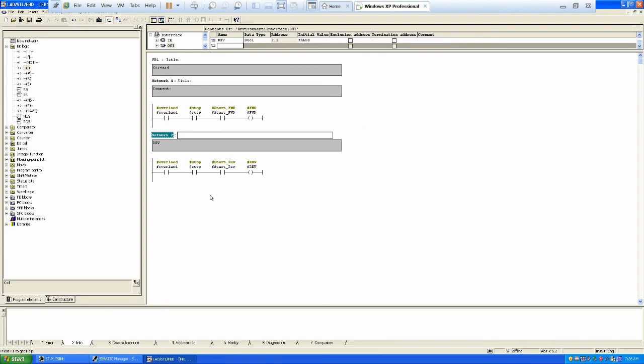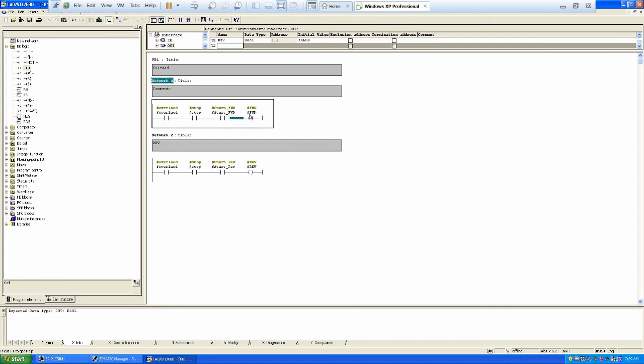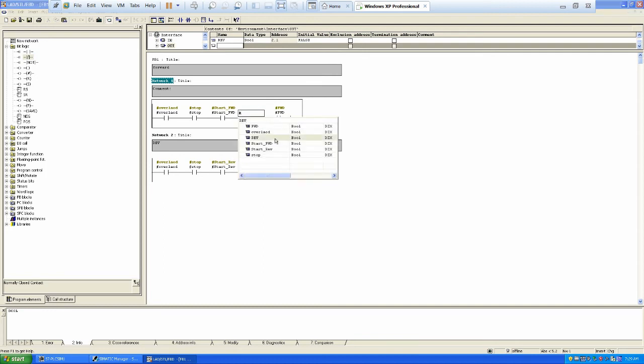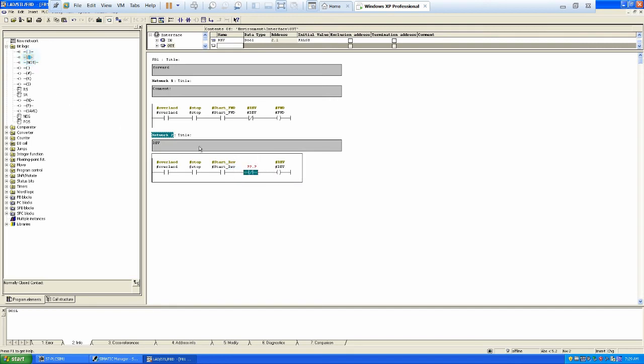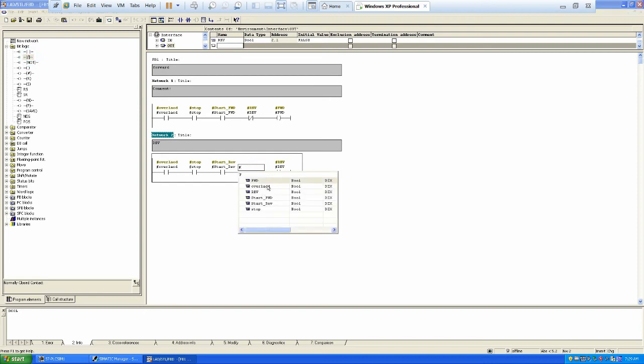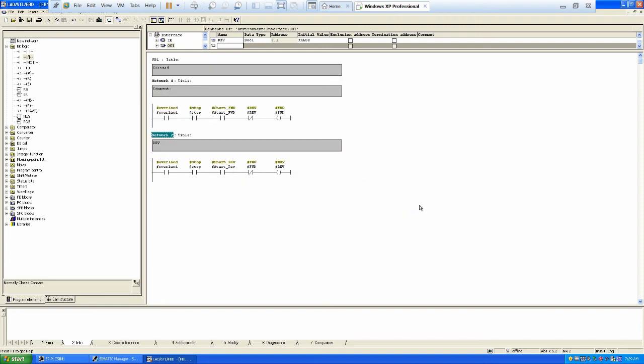Now we have one issue in that particular program — if you can run the motor in forward and reverse at the same time, because if somebody presses start forward and reverse at the same time, the motor will start running forward and reverse simultaneously, and what that is going to cause is it's going to burn the motor. In order to avoid that, we will make sure that when we are running the motor in the forward direction, it should check itself in the program that it is not running in reverse. We can check by monitoring that if the reverse output is not active, then it should go for forward. The same case applies for running the motor in reverse — you will check forward, and if the motor is not running in the forward direction, then it can go for the reverse direction.